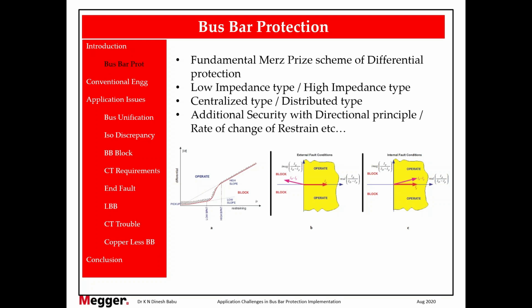That means all the current directions will be aligned towards the fault. This is called the directional principle. Let us assume a worst case. Out of the 10 currents, one current is not there because of some problem, maybe the CT wire is removed. Now what happens? Only 9 currents are there, but in reality 10 currents are there. In the relay there are only 9 currents reading. Due to this, there will be a differential current flowing in the circuit. However, the directional principle will not be satisfied because out of the 10, 5 currents may be entering, 5 currents may be leaving, but in the relay only 4 currents are leaving. That means 5 in one specific direction, 4 in some other direction. Therefore, the relay will understand that even though differential current is present, it has not satisfied the directional principle. So unless the directional principle is satisfied, the bus bar will not issue a trip command.